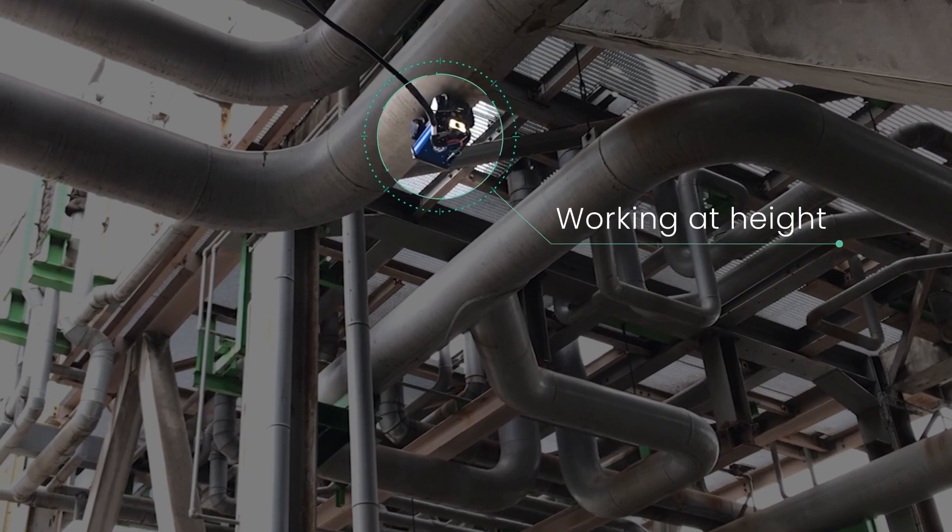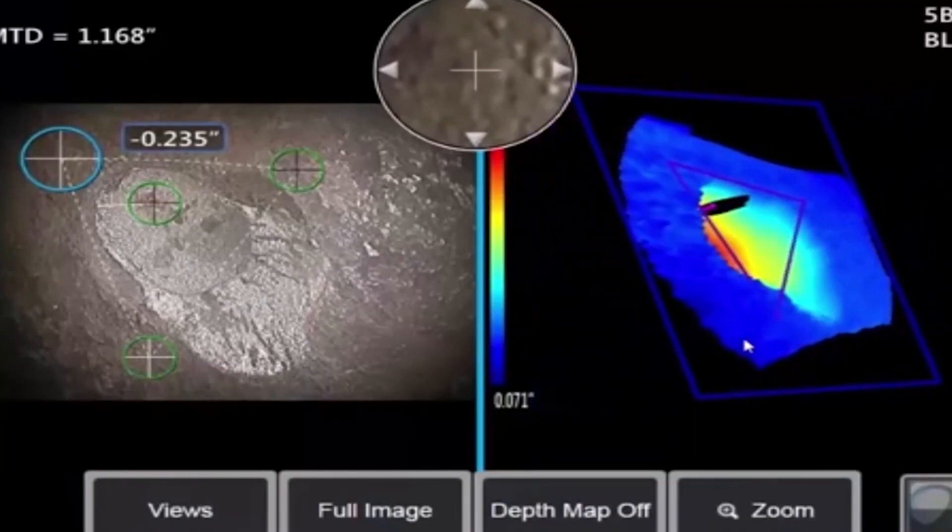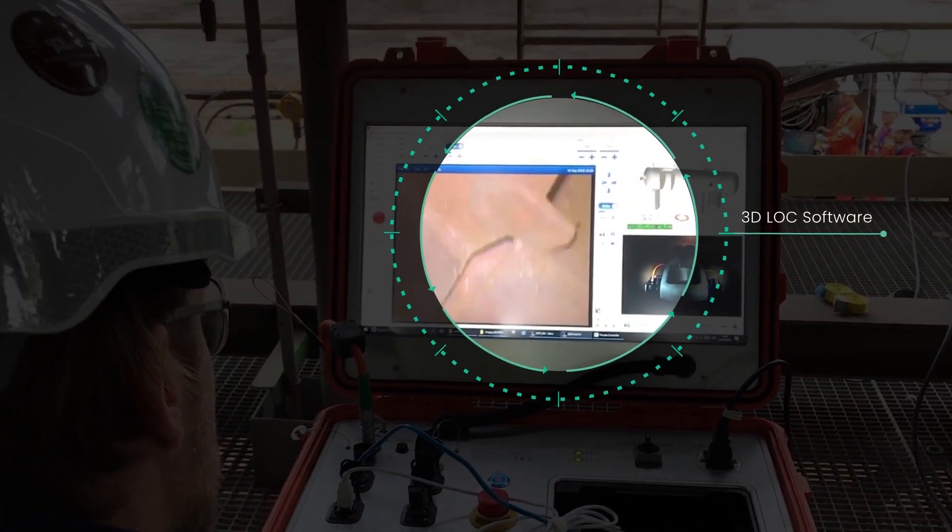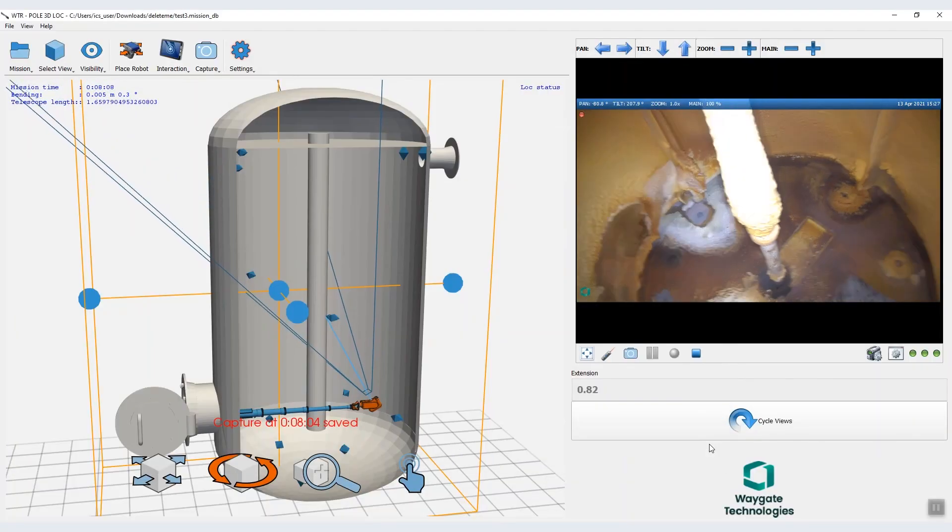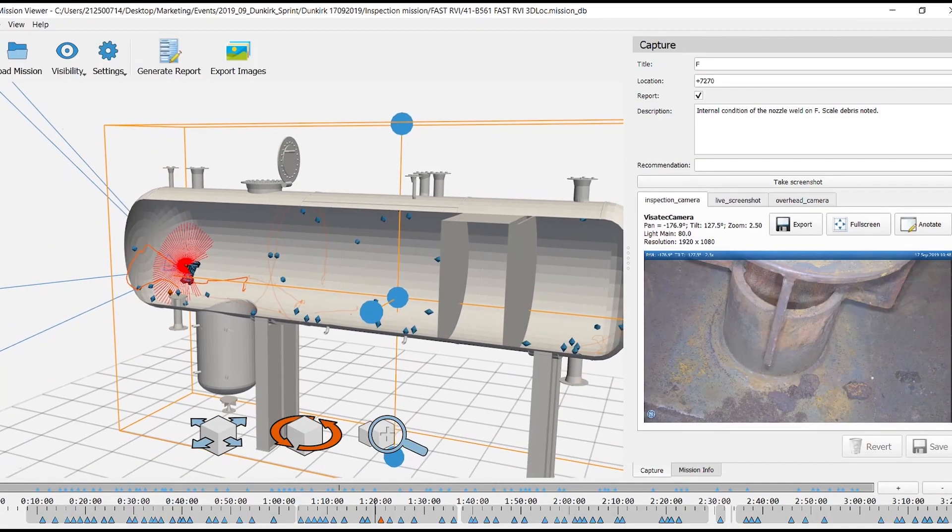With modules to collect ultrasonic, eddy current, video probe or structure light NDT data. With 3D LOC software, all inspection data is automatically tagged with the precise position inside the asset, while a digital twin containing all the inspection data is maintained.